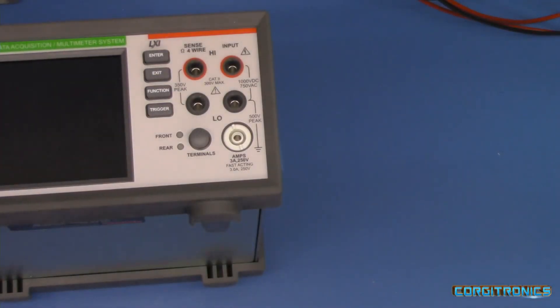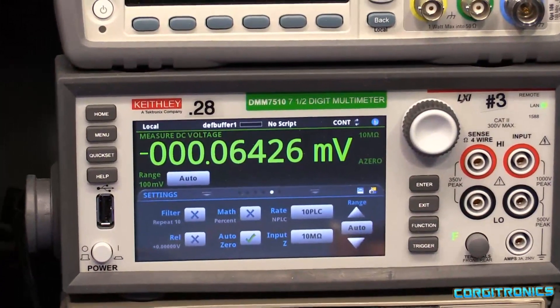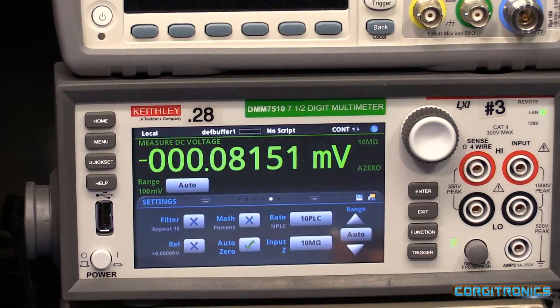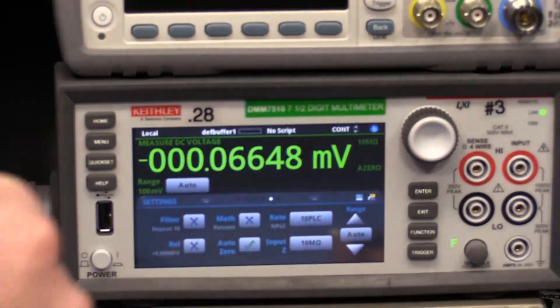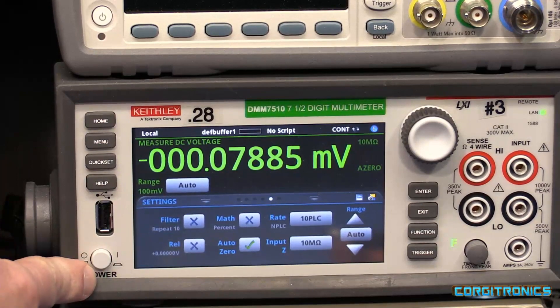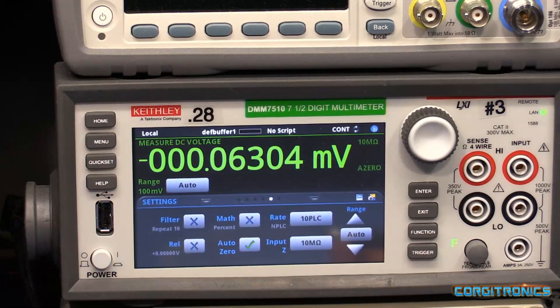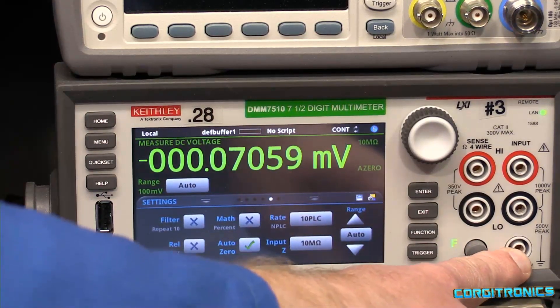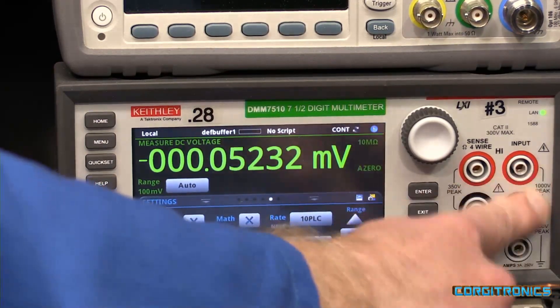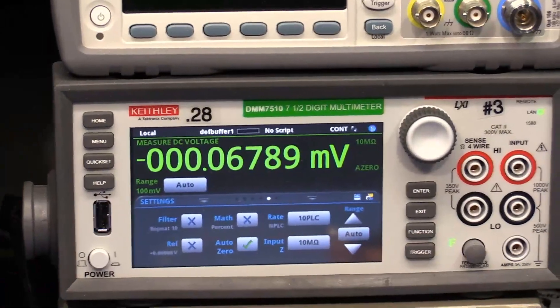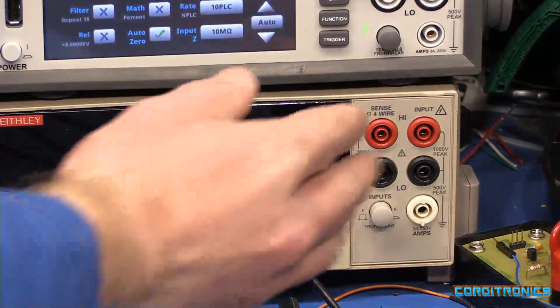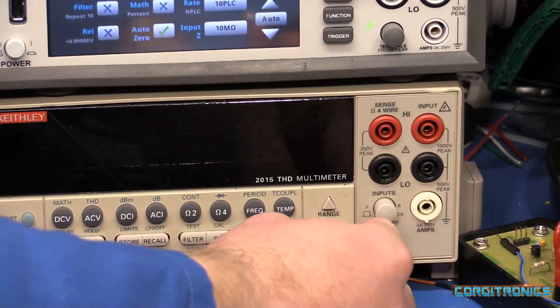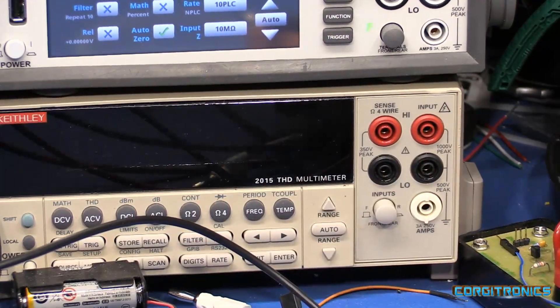And this is in a little bit of contrast to the DMM 7510, which is a very new meter. The 7510 has a jog knob here. That's different. We have a physical hard switch right here for the power, the vertical USB. And then the standard type that you would see on really most brands of meter, regular banana jacks, no front panel fuse capability. But that is how it used to be, because here down here on the old 2015 THD, we again have the front panel fuse. Just kind of interesting that they switched that out.